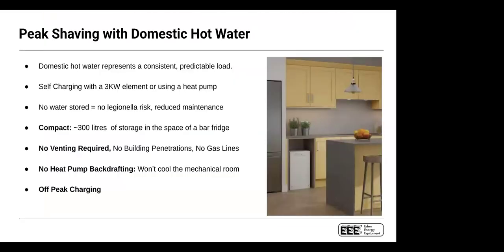So it's really cool from a domestic hot water standpoint because it represents a consistent and predictable load for the utility. It's a 3.05 kilowatt element, which means a 15 or 20 amp breaker, depending on what code compliance allows for you, if you look at that 80% rule. So it's got less electrical consumption than other devices because of the 50% lower standby loss and the fact it holds onto the BTUs. You can also take advantage of off-peak charging, which is really, really powerful. Don't generally pitch that as the first play. The first play is it has no moving parts, it doesn't store water, and you can fit it anywhere conveniently, and it's easily retrofittable.